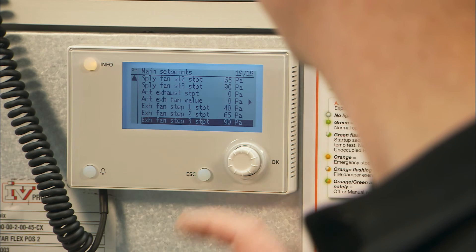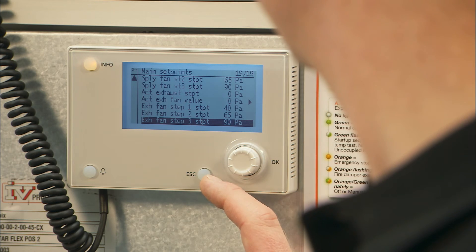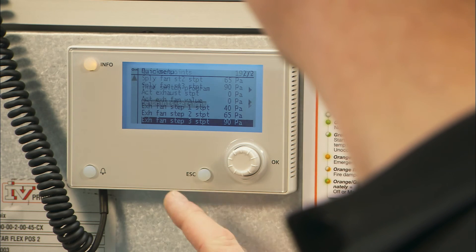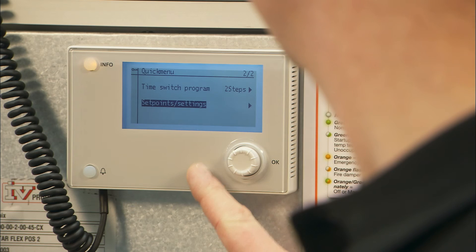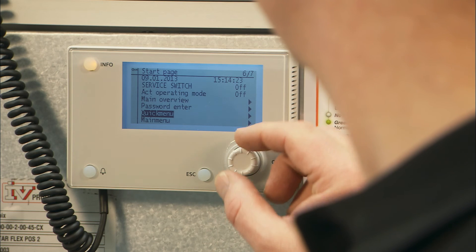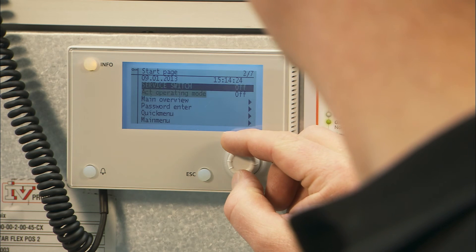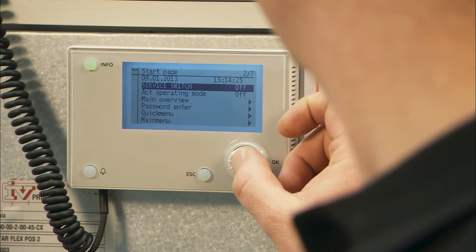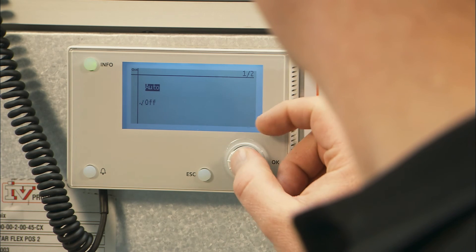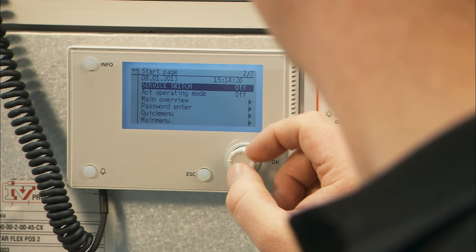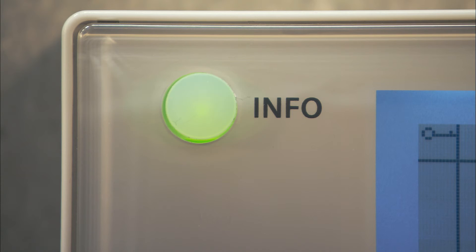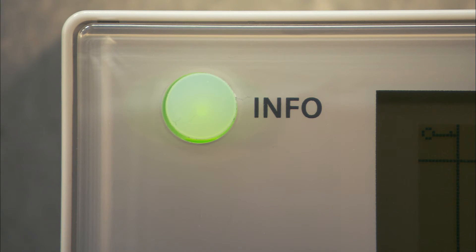Start the unit by moving back to the start page using the escape button and setting the service switch to the auto position. The information lamp will then blink green and thereafter show a steady green light once the unit has started.